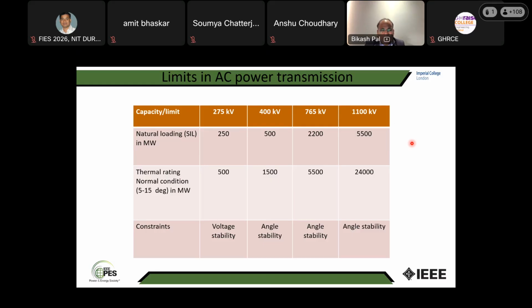Particularly if you carry more power than surge impedance loading, then what happens? More than surge impedance loading means the current in the line is large. If the current in the line is large, I square XL is more and omega C V square is less. So there is a net absorption, and there is no balance of the reactive power between the capacitance and the reactance. So this more reactive power has to come from the sending end.